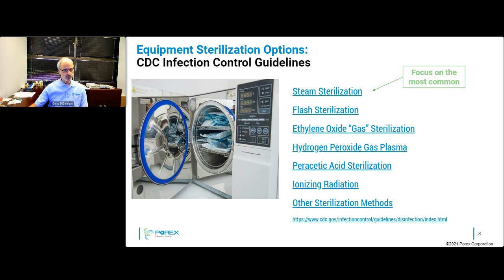So I'm going to go through a couple of the most common ways steam sterilization is used. The first one is, I would say, one-time use or open trays, and combining those two. One-time use are packages that are designed to seal around either a device itself. You can have just one part in there, or you can have a tray like shown in the picture with several parts in it. And then it's heat sealed typically or zipped around the device. And then it's put into an autoclave. Those tend to generate a lot of waste. Specifically, the packages are typically certain sizes, so sometimes a package goes mainly unused. And they tend to be fairly space inefficient.